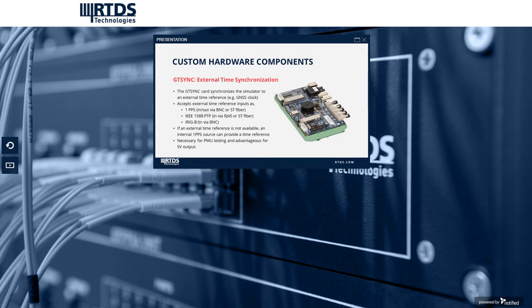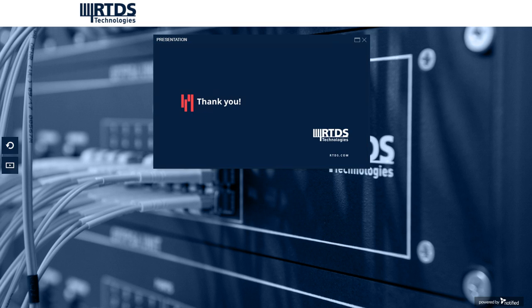And if an external reference isn't available, the GT Sync can actually provide its own time reference and act as a 1 PPS source. So this card is necessary if you're doing PMU testing with the RTDS simulator, and it's advantageous for SV output as well. Now I'll pass it over to Shane, and he'll give you some more details on the capabilities of the GTFPGA firmware, and he'll go through the demo.